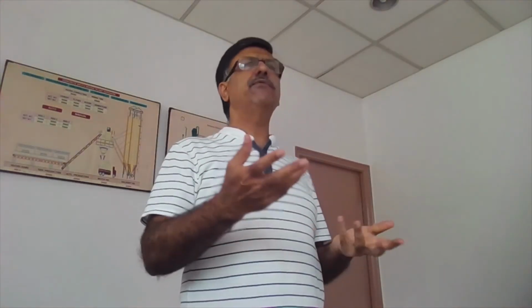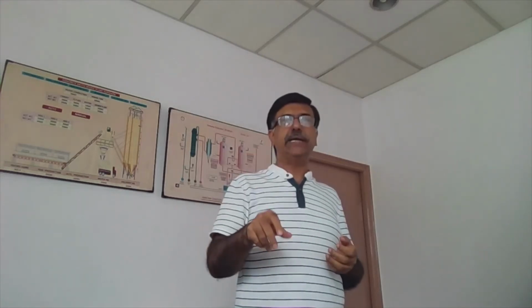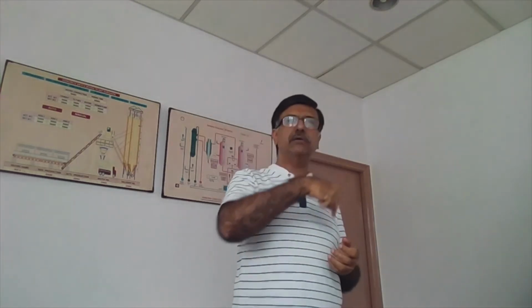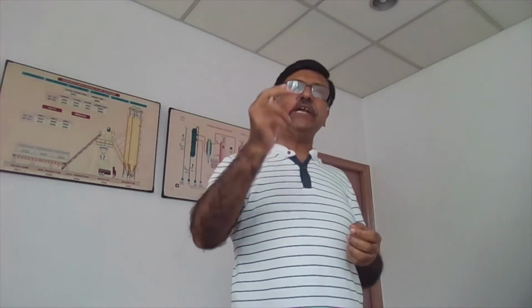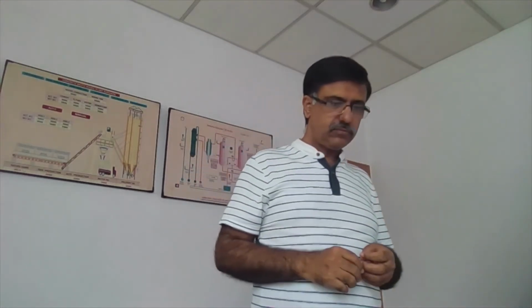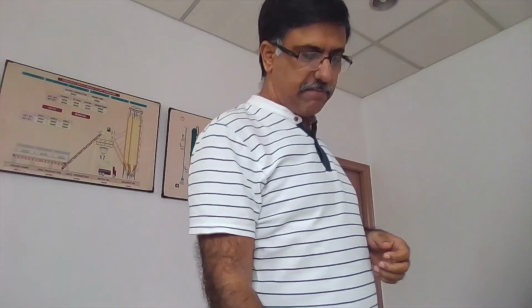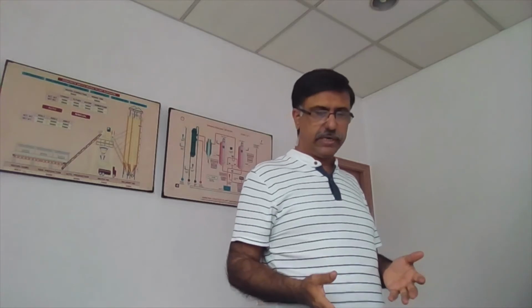Where it is read only, for example, voltage in a multifunction meter, you don't want to write onto that. You only want to read. But if you have a PLC where you are measuring voltage and you want to change the servo setting, you'll have an output where you'll be able to change the servo setting and thereby the voltage will change. So you need to write into the PLC. So you will have a write functionality. So you have a read only or read write facility. This is also what you need, a memory map of the devices so that you know how to address, how to reach there. Okay.